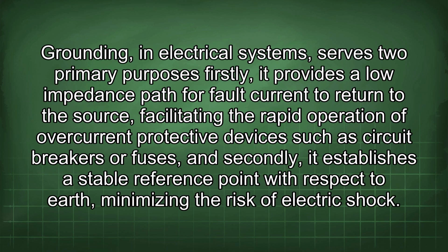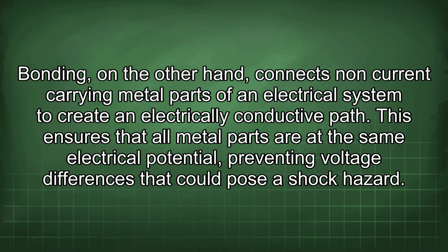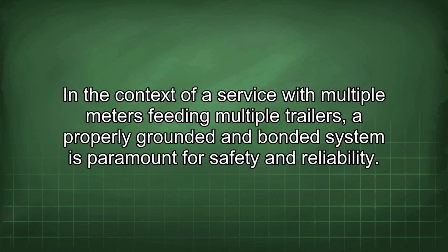Grounding in electrical systems serves two primary purposes. Firstly, it provides a low impedance path for fault current to return to the source, facilitating the rapid operation of overcurrent protective devices such as circuit breakers or fuses, and secondly, it establishes a stable reference point with respect to Earth, minimizing the risk of electric shock. Bonding, on the other hand, connects non-current carrying metal parts of an electrical system to create an electrically conductive path. This ensures that all metal parts are at the same electrical potential, preventing voltage differences that could pose a shock hazard. In the context of a service with multiple meters feeding multiple trailers, a properly grounded and bonded system is paramount for safety and reliability.